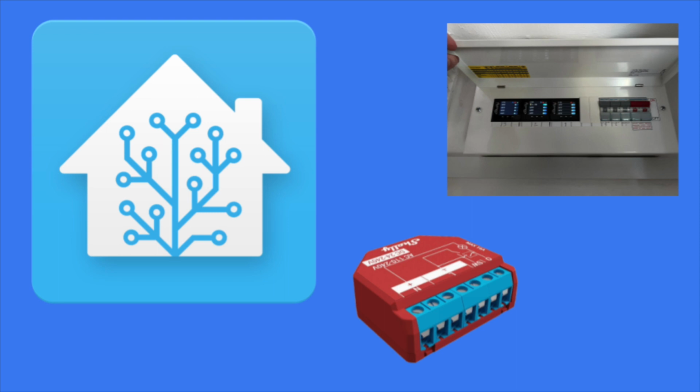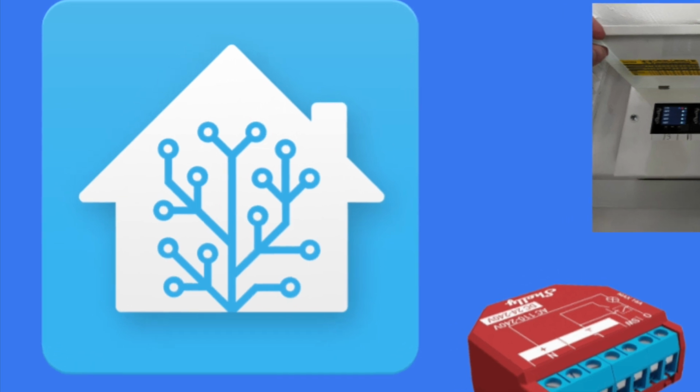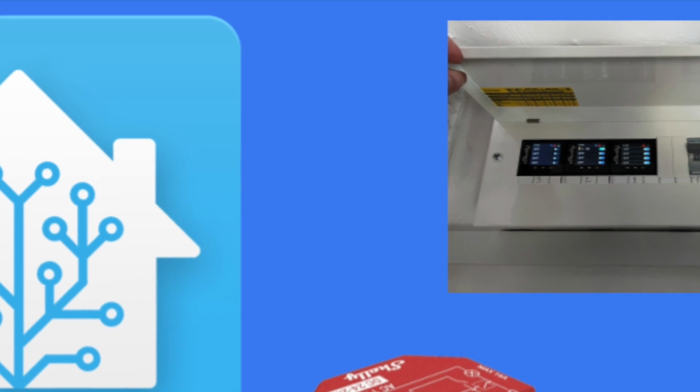We intended to analyse this stuff from the very beginning, so when we installed the solution, we had it with ways of collecting data. We've integrated the far infrared panels into Home Assistant, which is a home automation system, using Shelly Pro 4PM control units. These are 4-channel relays controllable over either Wi-Fi or Ethernet, and DIN rail mounted, and we've had these installed in a sub-consumer unit of the house by a local electrician. These controllers allow remote controlling the state of the heaters, as well as recording power and energy used by the heaters. And where that hasn't been practical, we've used single-channel outlet mounted Shelly 1PM modules.